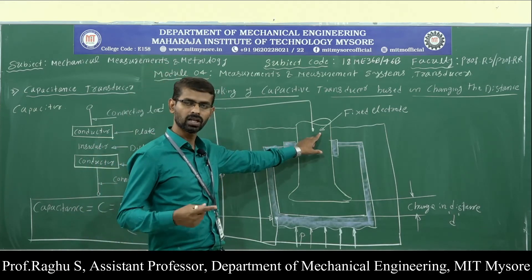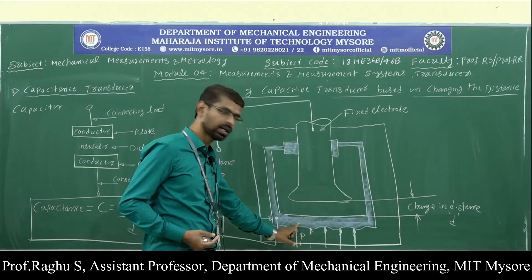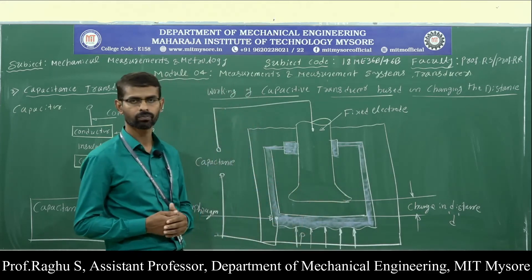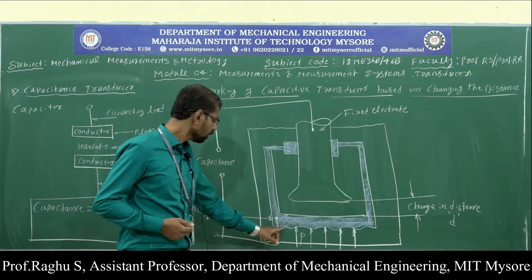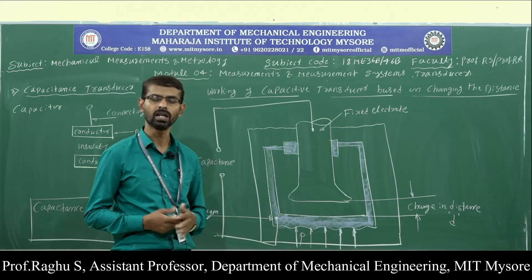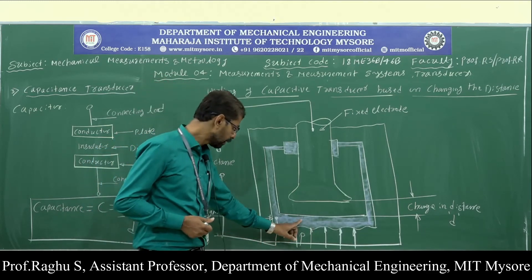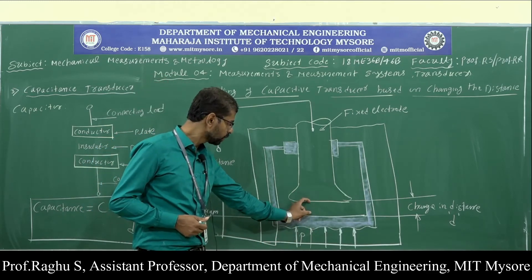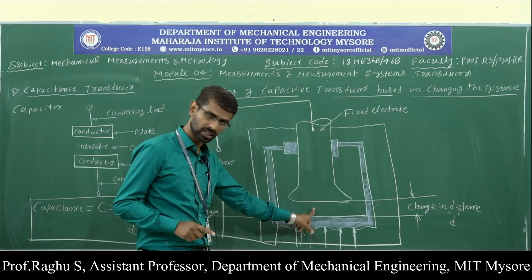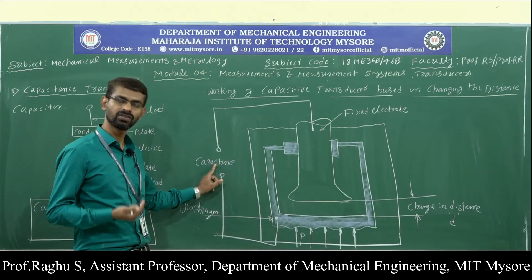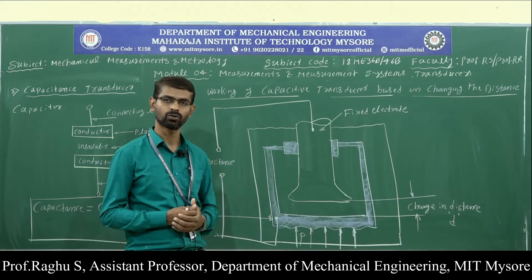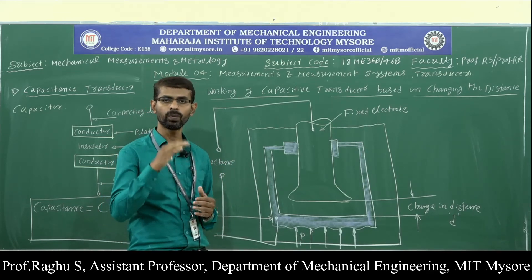In the capacitive transducer, a fixed electrode acts as one plate and a diaphragm acts as the other plate, separated by a small distance d. The pressure to be measured is applied onto the diaphragm. Since the diaphragm is a flexible material, it undergoes deflection. When the diaphragm deflects, the distance between the fixed electrode and diaphragm changes. When the distance decreases, capacitance increases. The change in capacitance can be measured and taken as the measurement of pressure.